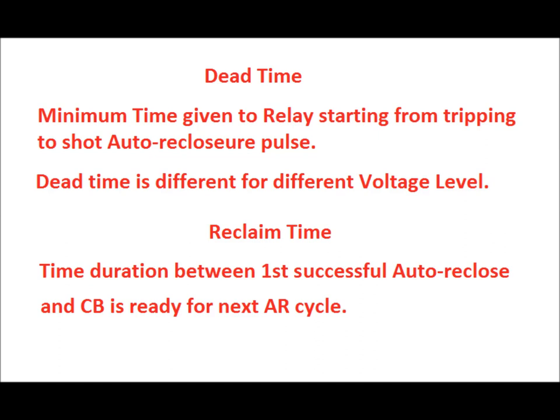Dead time is the minimum time given to the relay, starting from tripping to the auto reclose pulse sent to the circuit breaker. For example, after the relay sends a trip signal and the circuit breaker opens, it waits for a certain period defined at the relay, after which the relay sends an auto reclose pulse to the circuit breaker. This time duration is called dead time, and it differs for different voltage levels.